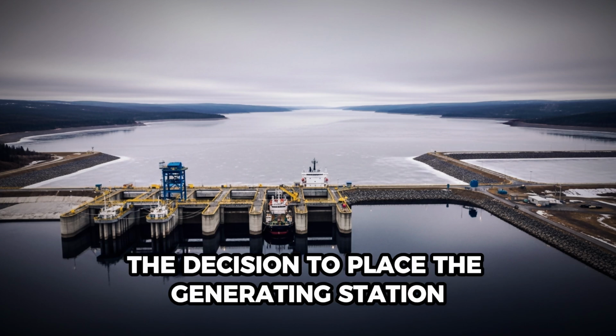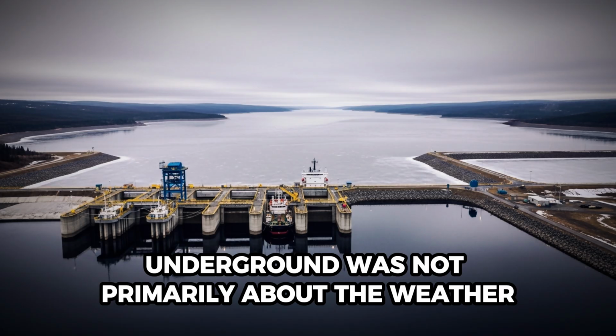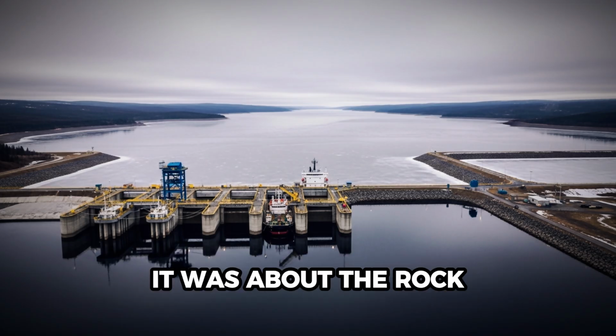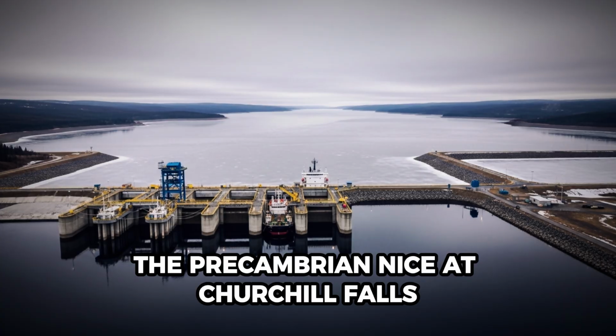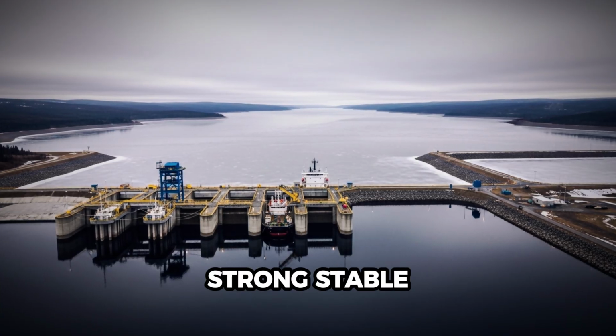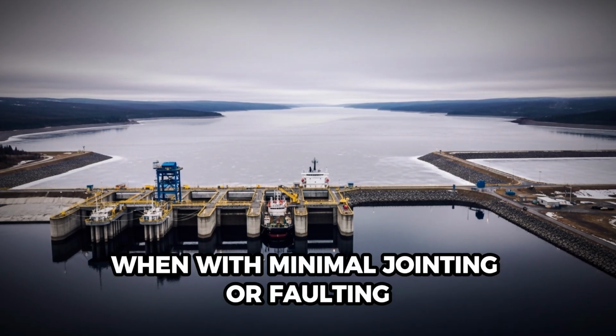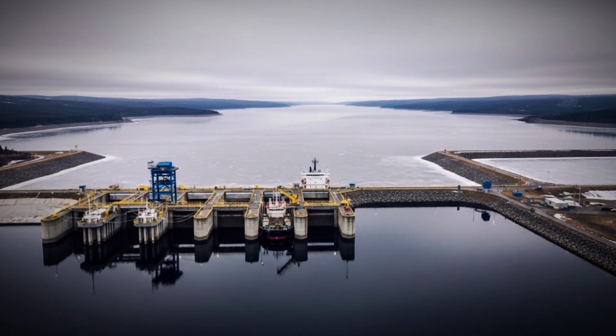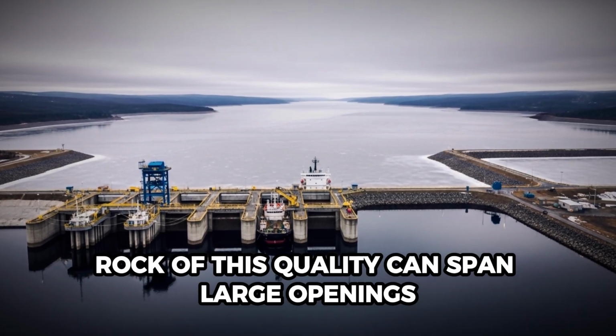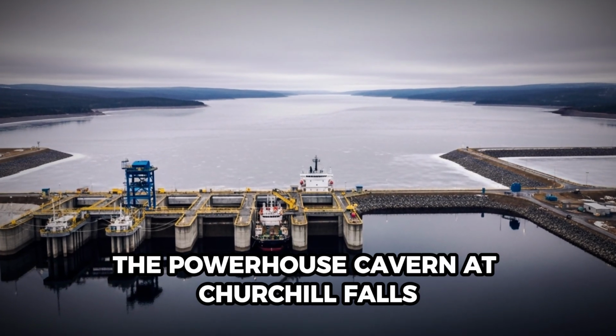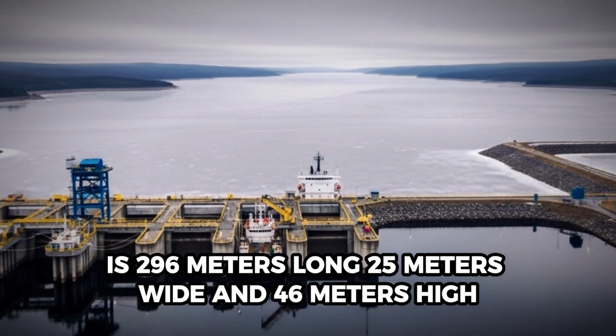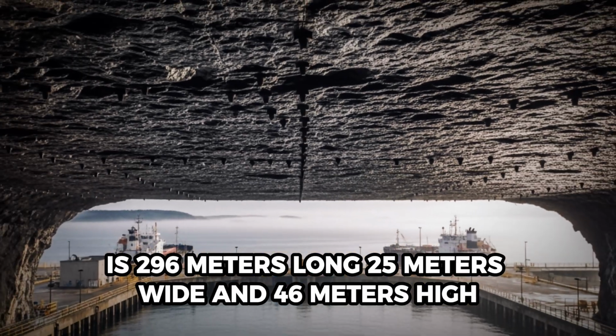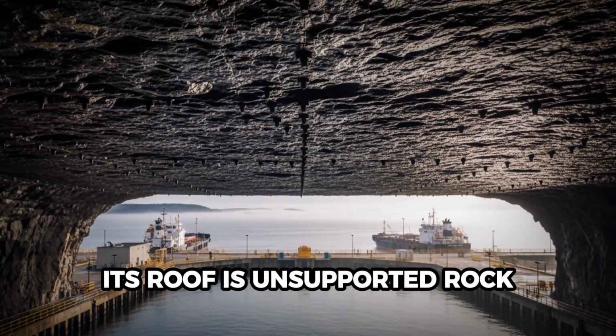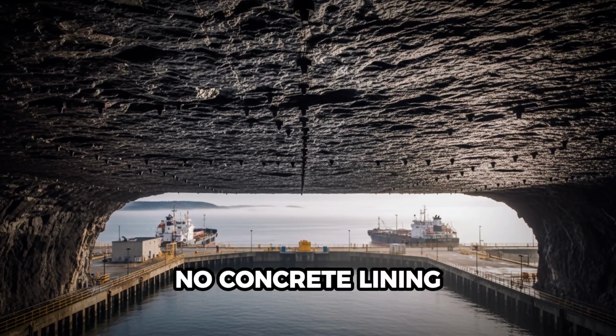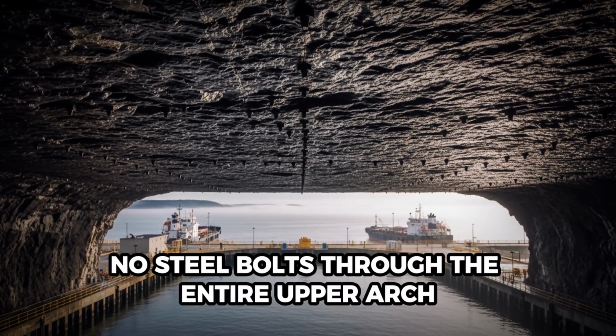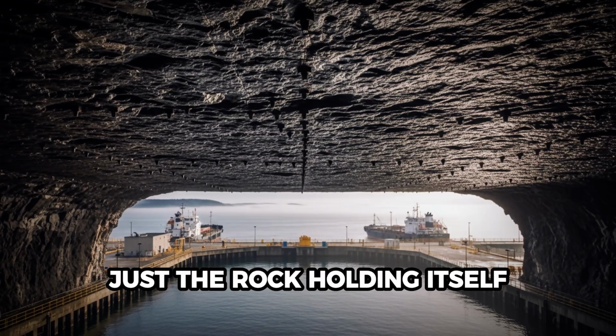The decision to place the generating station underground was not primarily about the weather. It was about the rock. The Precambrian gneiss at Churchill Falls is exceptionally competent, strong, stable, with minimal jointing or faulting in the sections where the cavern was sited. Rock of this quality can span large openings without support. The powerhouse cavern at Churchill Falls is 296 meters long, 25 meters wide, and 46 meters high. Its roof is unsupported rock. No concrete lining, no steel bolts through the entire upper arch. Just the rock holding itself.